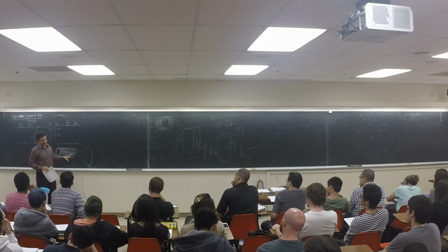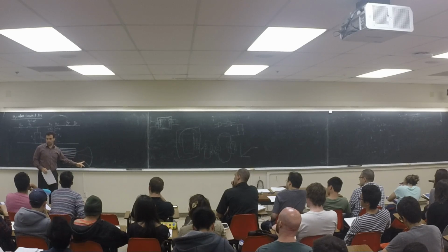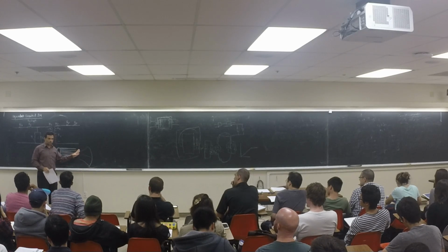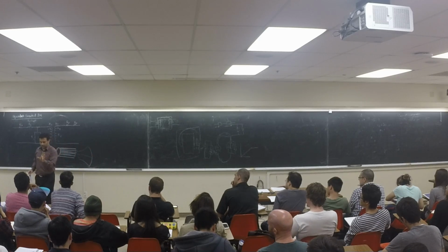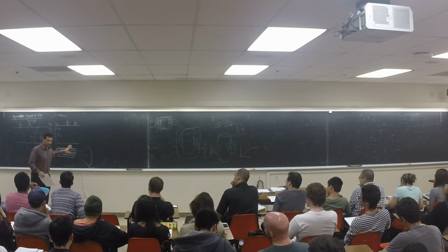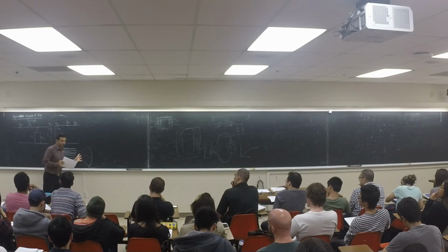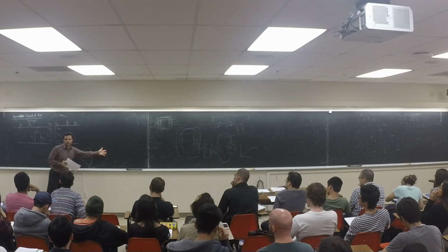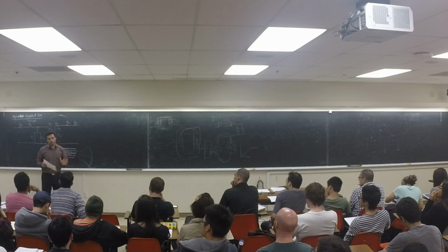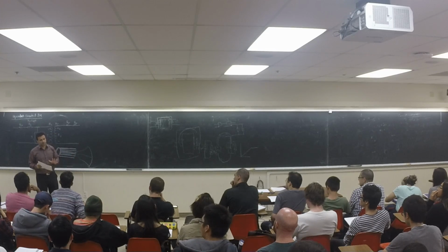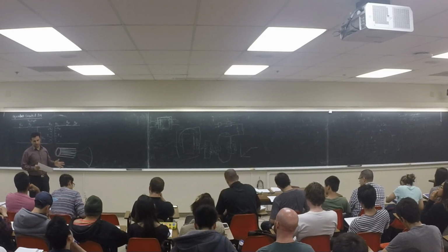And simply you can see, the squirrel cage machines are much cheaper than the wound rotor. Why? Because in the wound rotor, you have to bring these wires out, right? Like the DC machine, they have to have a commutator. But see, this one is moving. Think about it. This one is moving. Now, you have to come up with an arrangement. You can bring these 3 wires out. They put slip rings for that, very similar to the commutator. So those things will make the machine more expensive. The squirrel cage machine is the cheapest one compared to the wound rotor and compared to the DC machine.